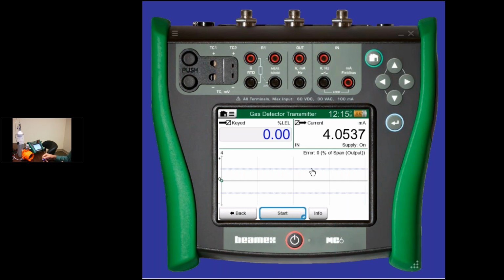So to enter calibration mode, I just put my magnet here on the glass, and I can see it's kind of blinking. I guess you can't see that, but I can. I can move it down. Well, it's looking really good now. I'm just going to leave that alone. So I'm going to hit menu again, and it's now in span mode. So now I'm going to hook this guy back up and turn my gas back on. And let's get it back up to range here.